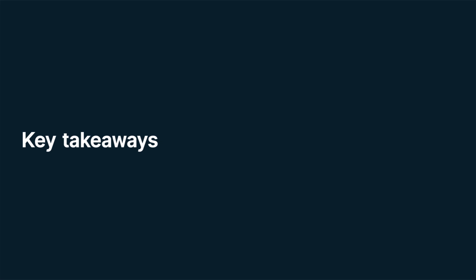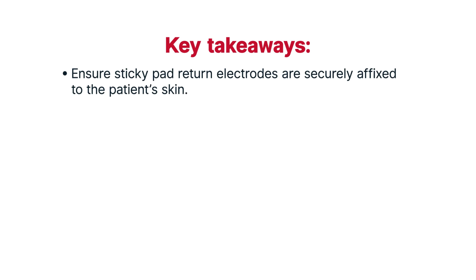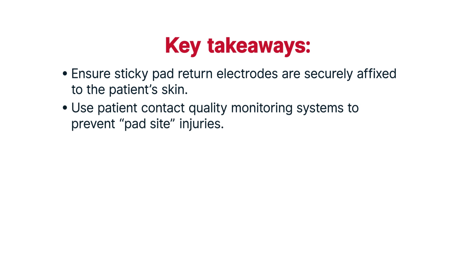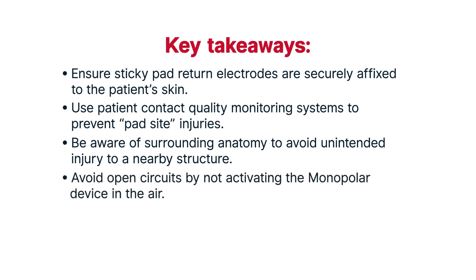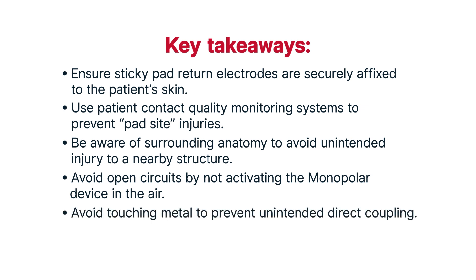Key takeaways and tips. In review, specific measures to reduce risk during electrosurgery include: ensure sticky pad return electrodes are securely affixed to the patient's skin; use patient contact quality monitoring systems to prevent pad site injuries; be aware of surrounding anatomy to avoid unintended injury to a nearby structure; avoid open circuits by not activating the monopolar device in the air; avoid touching metal to prevent unintended direct coupling; check the insulation on all instruments before use. This is the last video in this critical concept video series.